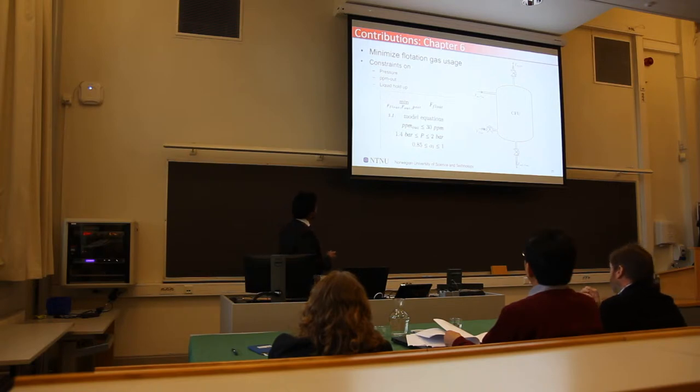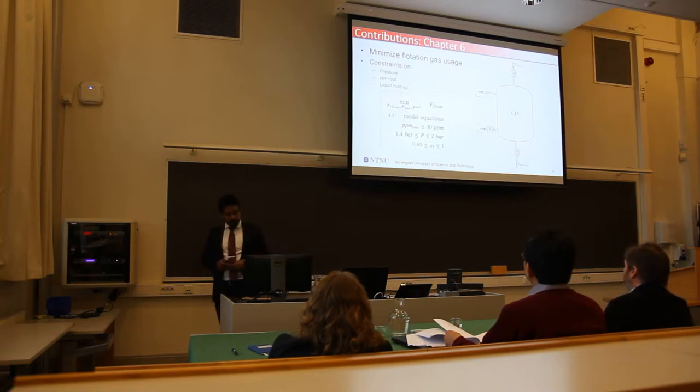To do that, we formulate this optimization problem, where we want to minimize the use of flotation gas and constrain it with model equations and certain other things. The PPM out should be less than 30 PPM, which is the requirement by OSPAR. The pressure, we consider to be between 1.4 bar and 2 bar. We assume that there are some operational requirements which ask them to be between those numbers.